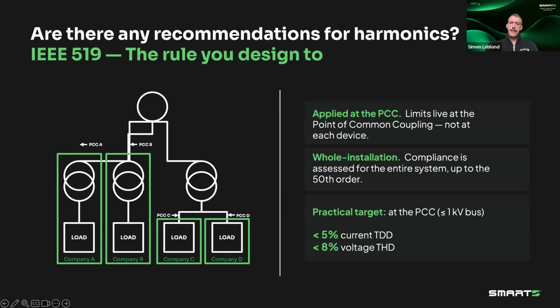Second thing I want to highlight is that the current version of IEEE 519, which is 2022, only goes up to the 50th order of harmonic. There is talk that future revisions will go higher, but for now there's this blind spot between the 50th order and EMI standards where anything goes. And maybe the last thing I want to mention about IEEE 519, without going into the details of the table: if you want a practical target, think less than 5% current TDD and less than 8% voltage THD. Current is usually what you care about. Voltage distortion is what the utility cares about. But both are important, as we've discussed before.